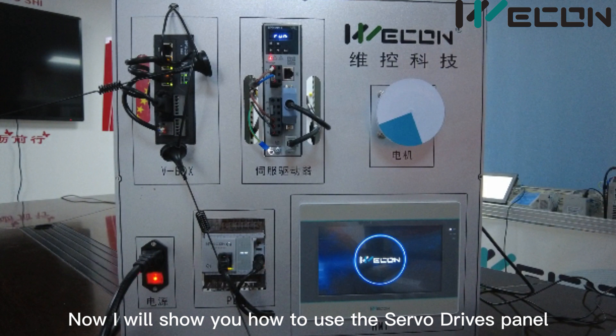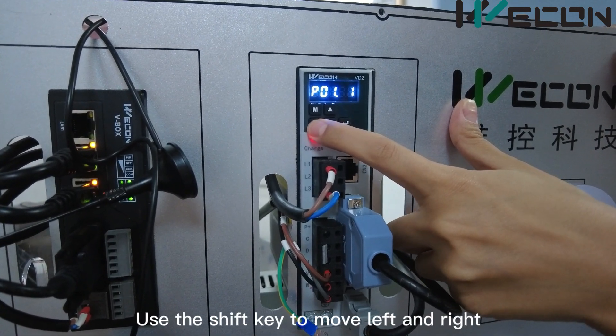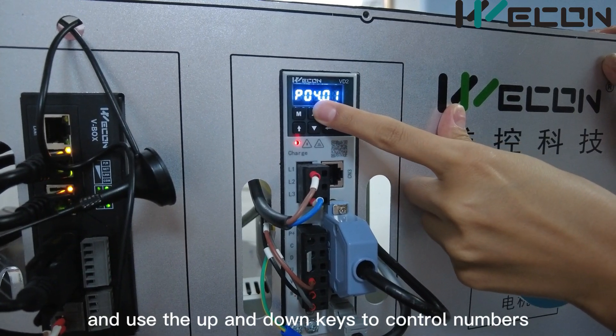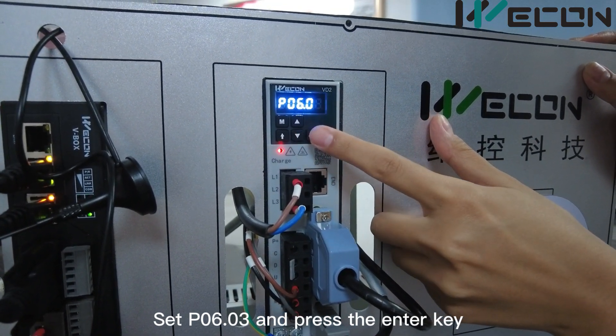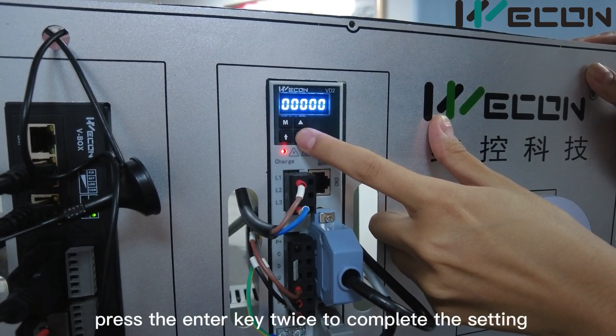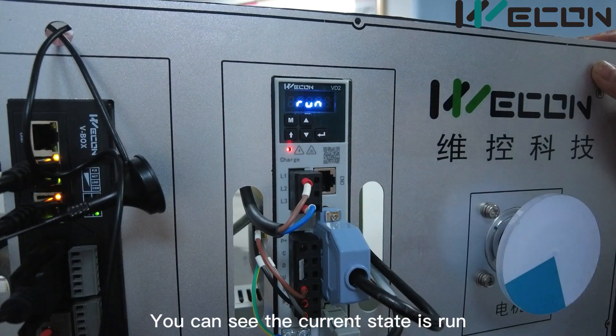Now I will show you how to use the Servo Drive panel to set the parameters. Press the Mode key to select. Use the Shift key to move left and right, and use the up and down keys to control numbers. Set P6.3 and press the Enter key. Set the value to 1, press the Enter key twice to complete the setting. Press the Mode key and you can see the current state is run.